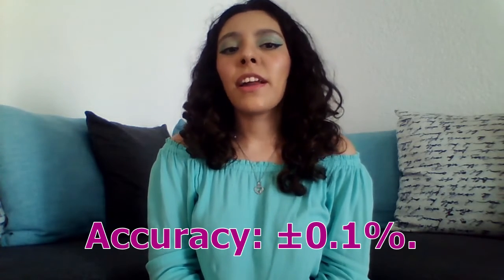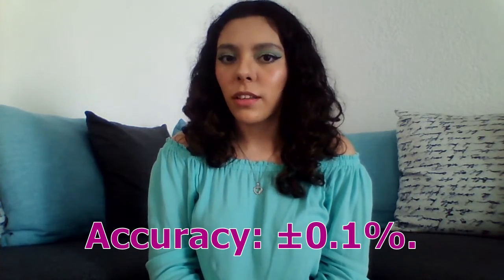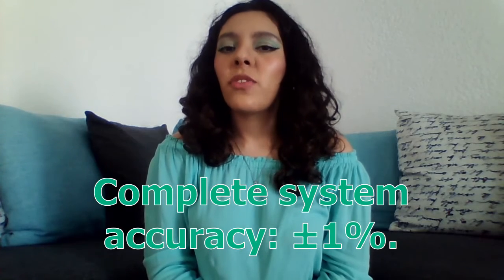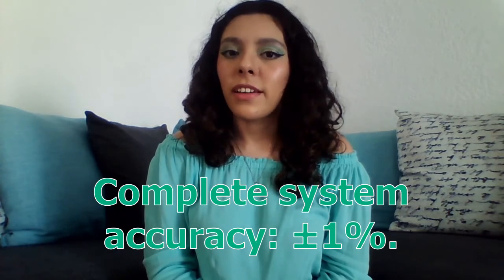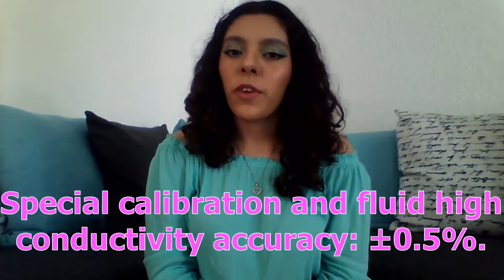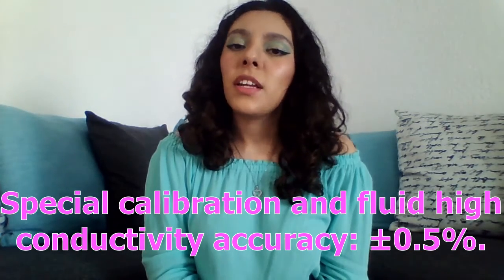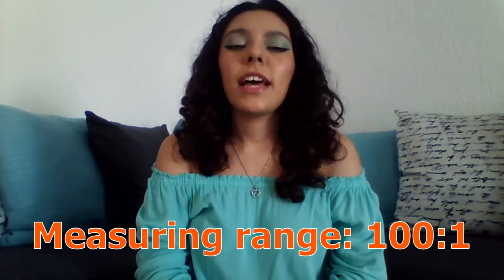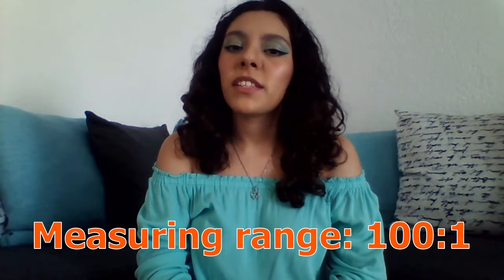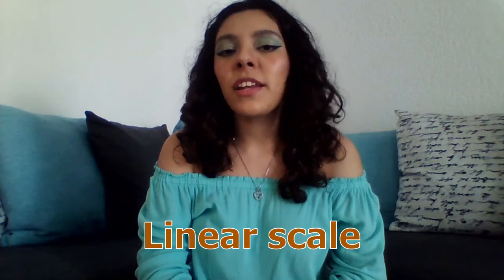Calibration of this instrument is normally done at the factory, and no adjustments are required before commissioning. Simply fill the tubing with liquid, connect the instrument, and give the system time to warm up and stabilize. Magnetic meters have a high accuracy of ±0.1%. With the complete system, it has an accuracy of 1% over the entire scale, and an accuracy of ±0.5% can be achieved with a special calibration and if you have a high conductivity. It has a measuring range between the minimum and maximum flow of 100 to 1 with a linear reading scale.